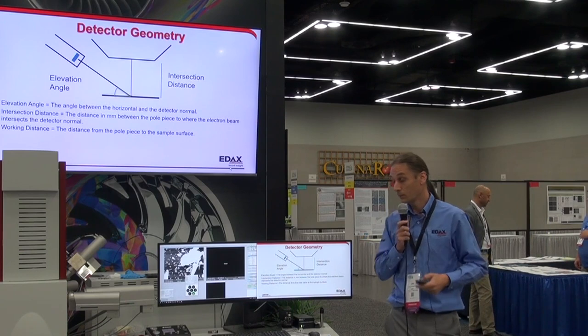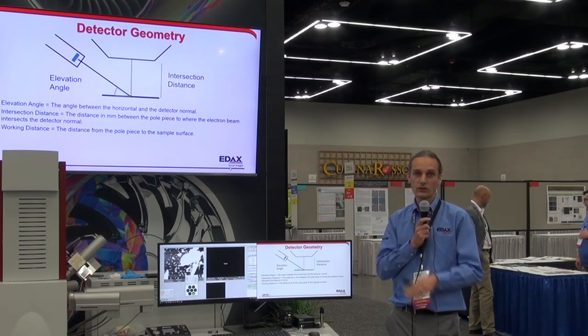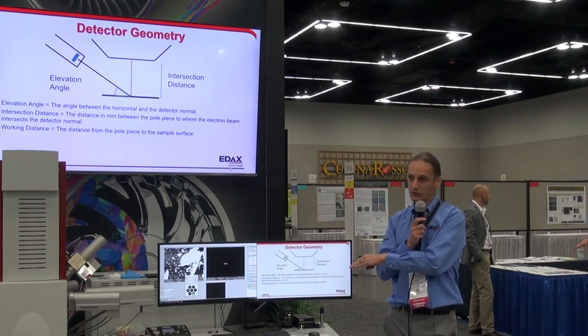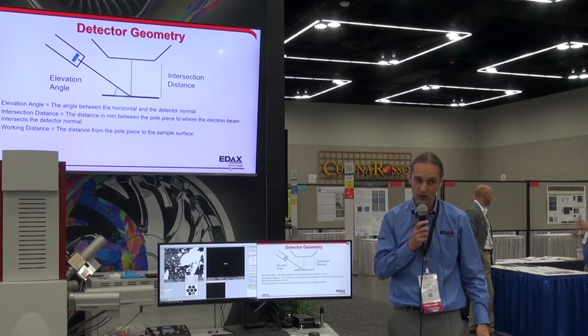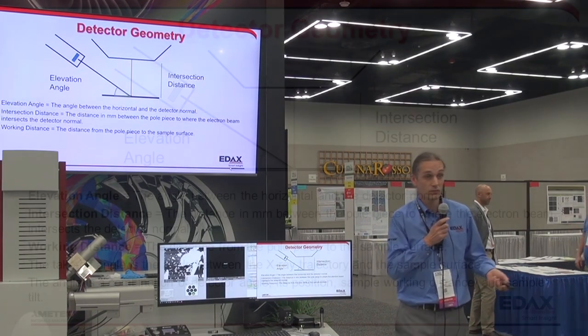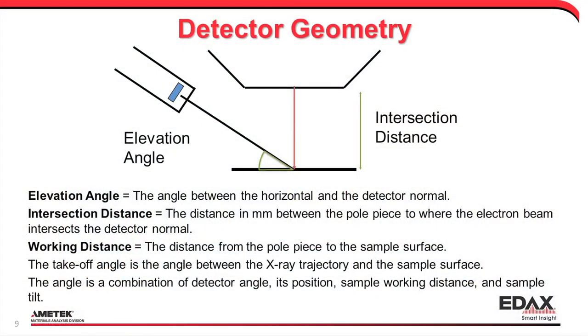On this microscope, the designed intersection distance is 15 millimeters, so we would want to be around 15 to have optimum collection. On other microscopes it may be 8.5, or on a FIB it may be 5 or even 4 millimeters — it changes system to system. In general, your working distance should be identical to the intersection distance to be at the sweet spot.